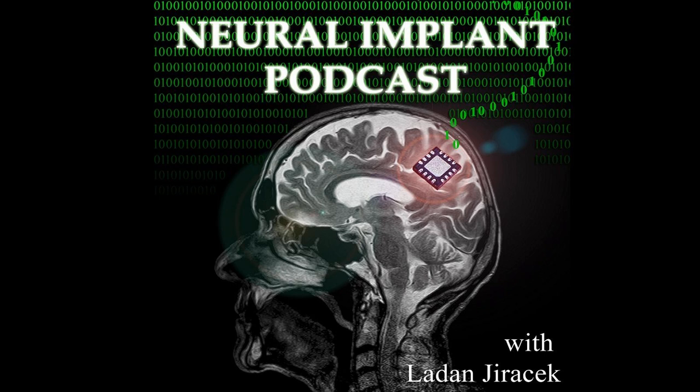Well, I think previously you've talked with Walt Voigt, and they have mechanically adaptive devices, and there are other examples out there of mechanical adaptive devices that are typically to accomplish the immediate insertion needs. They're stiff enough to be inserted, and then they soften in the body. Or you have some mechanical adaptation ability within the backbone of the device. We haven't yet incorporated how that might be used to keep the device going long term, for example. So you could have microdomain mechanical changes that might make things better for the device tissue interface. And the corresponding thing can easily happen in the electrical or chemical domain as well.